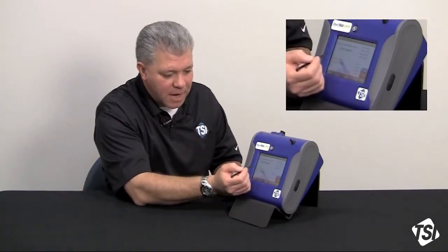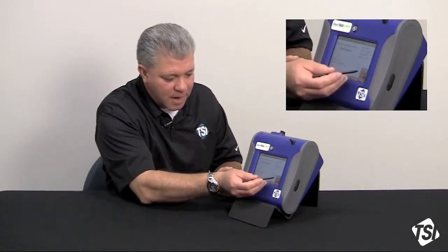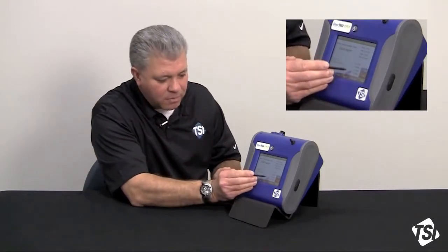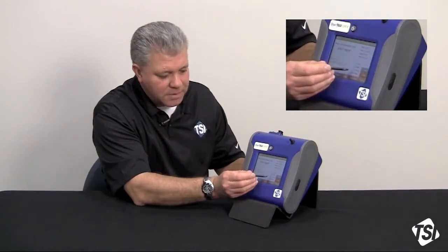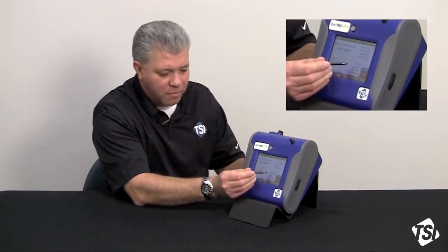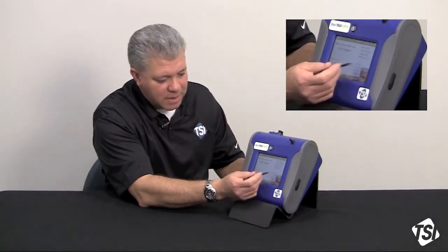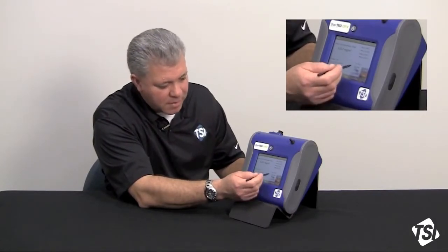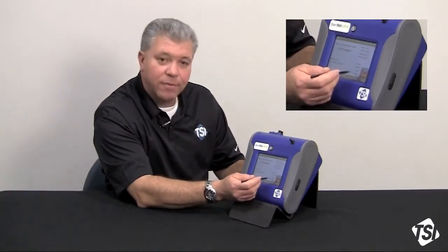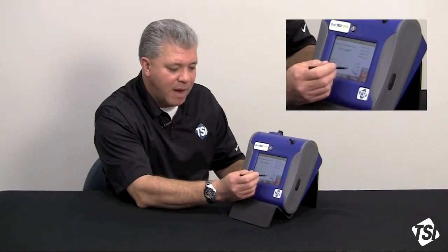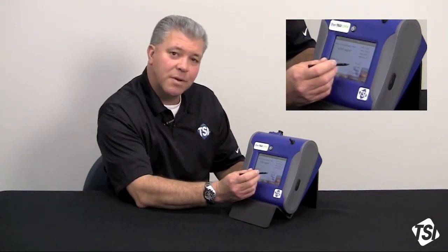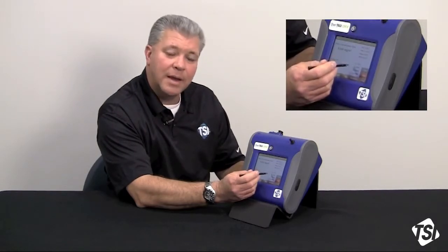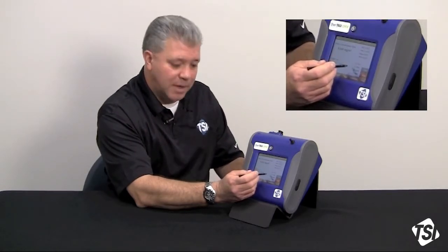So we've got all of our size fractions. Again, you've got your stats buttons, and then over here you have some indicators that are relative to the instrument's performance right now. We don't have a STEL alarm set. We have a pump, a laser, and a flow. So if you ever have an error with any of these green radial buttons, they'll actually turn to red in color, indicating that there may be an issue with the instrument.